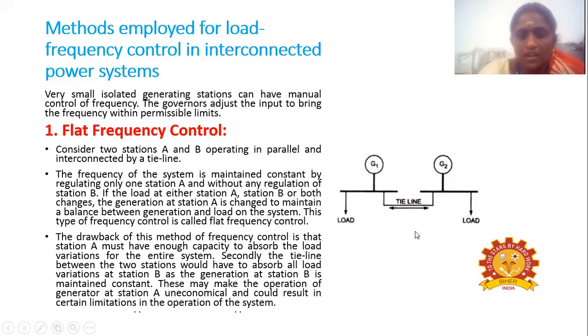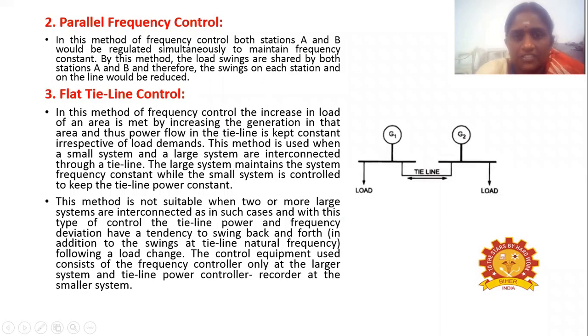The main drawback of this method is that station A must have enough capacity to absorb the load variation of the entire system, and the tie line between the 2 generators would have to absorb all the load variations. So these are the 2 drawbacks. Because of these reasons, the operation at generation A will be uneconomical, and it will result in a certain limit in the operation of the system. To overcome this, we can go for the next method of frequency control, that is parallel frequency control.